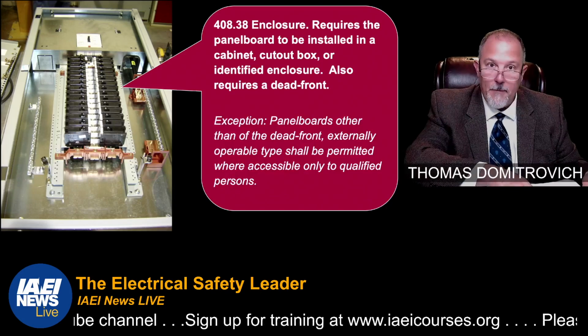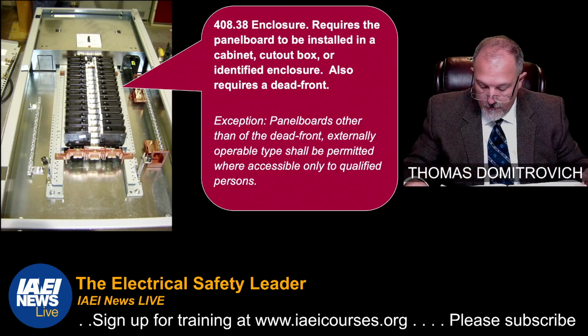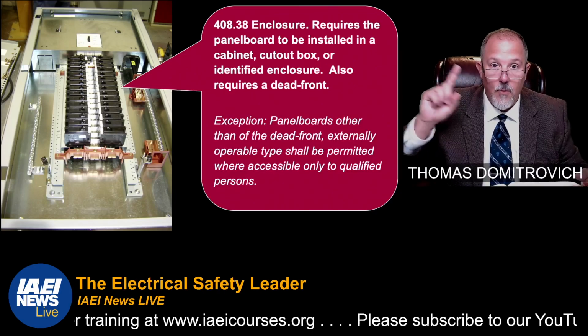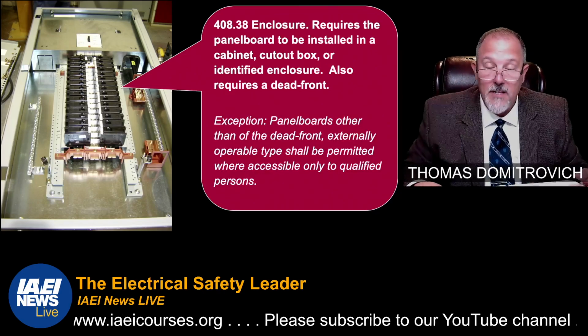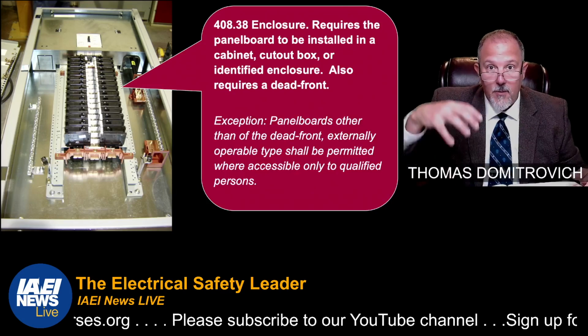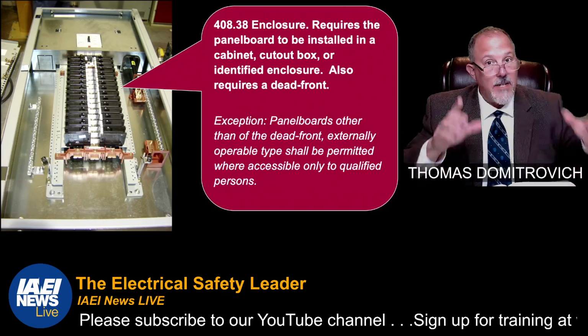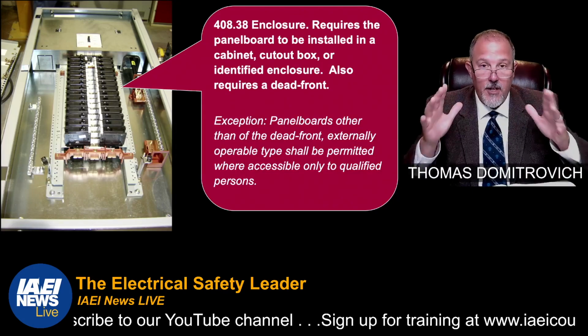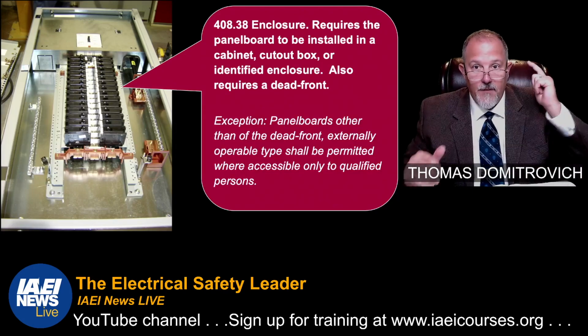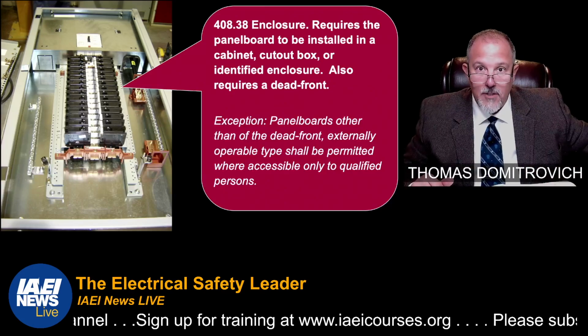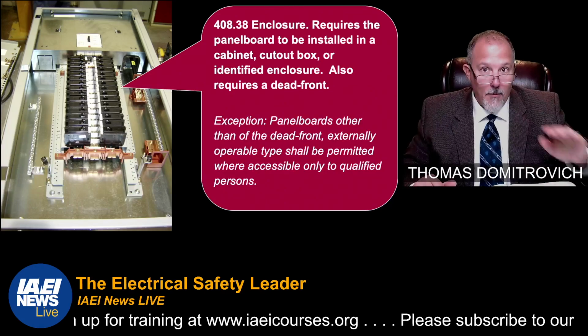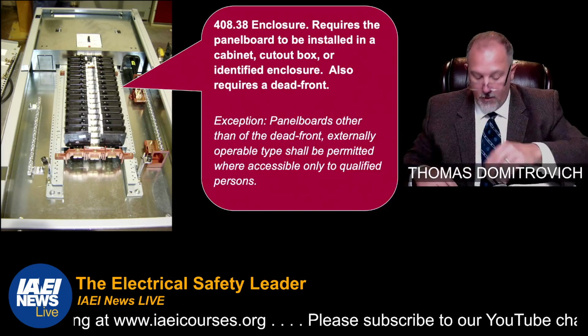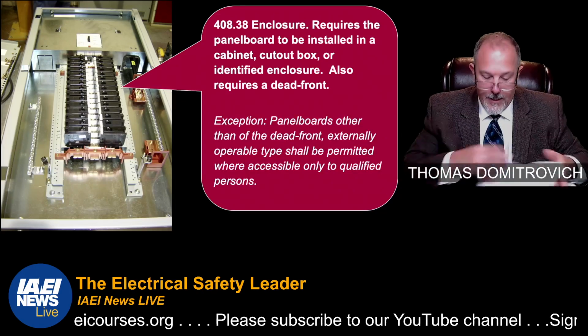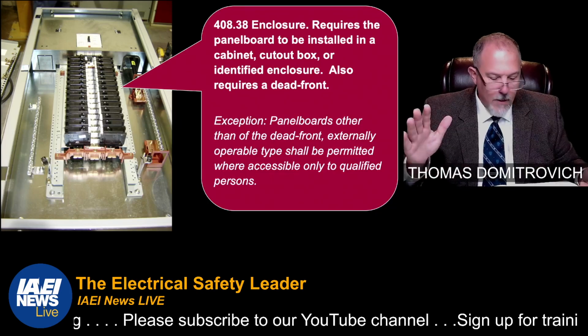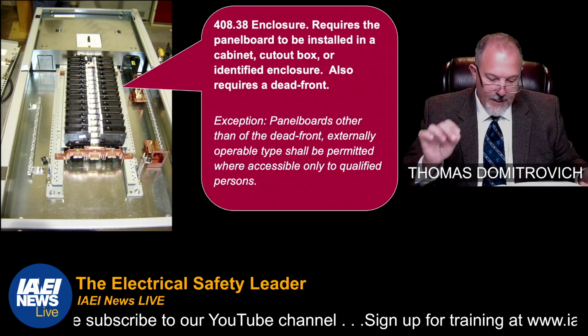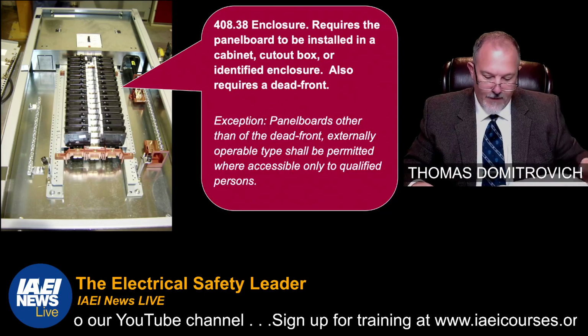Part 4 starts at 408.50. Part 3 starts at 408.30. So 408.38, we know, is in the panelboards part. So any of the requirements only deal with panelboards. That's another important thing to remember. You've got to understand where you're at in the code. If you're looking at 408.38 and thinking you're going to apply it to a switchboard or switchgear, that would be wrong because you're only in part 3, panelboards. All right. And then there's a part, I said part 4. I don't know if I did or not. Construction specifications. And that starts at 408.50.